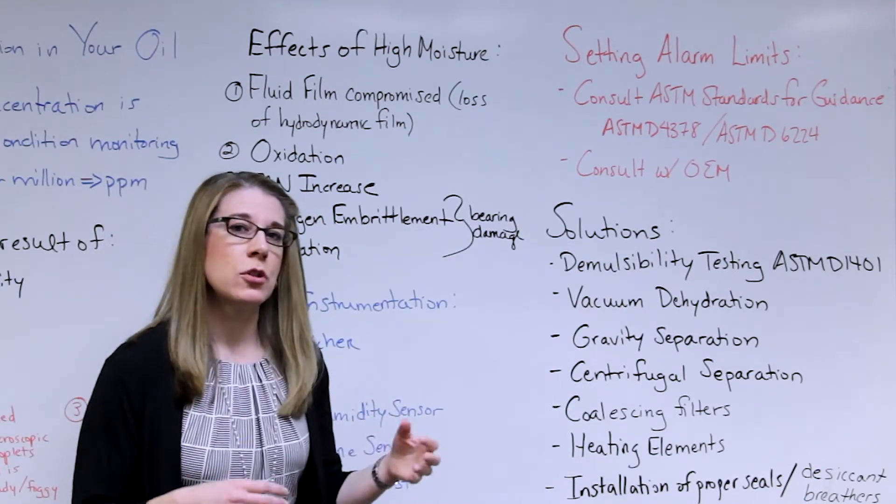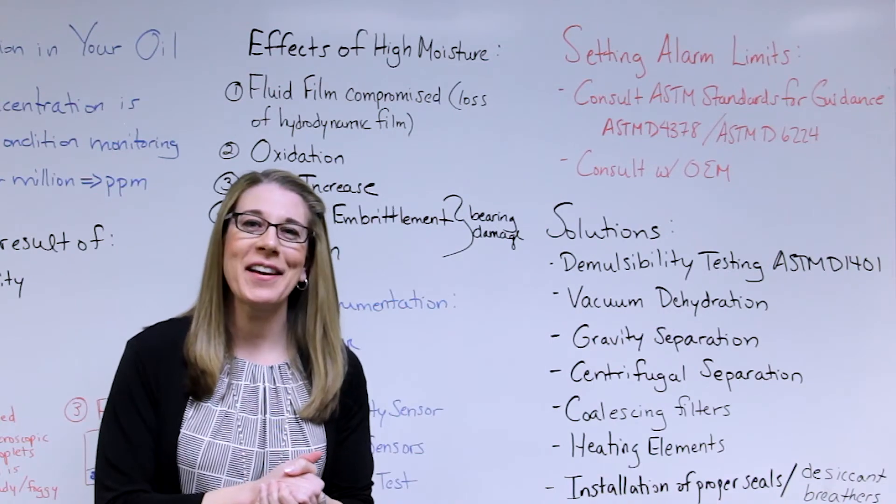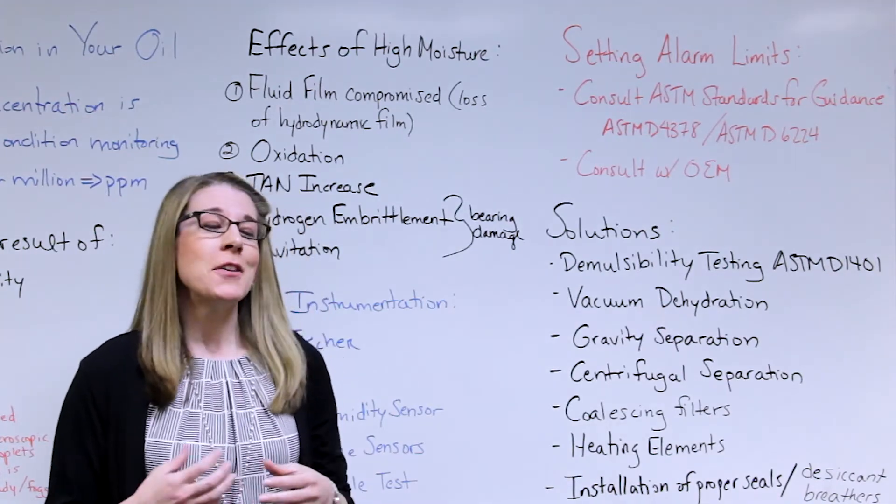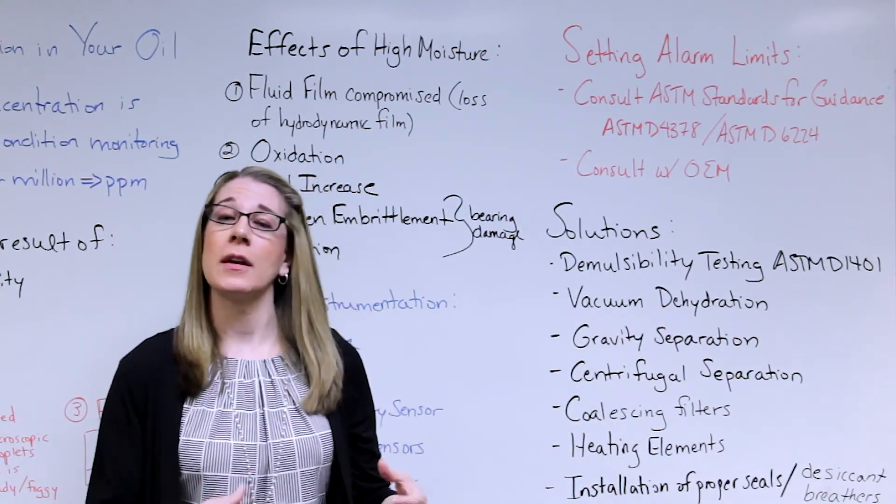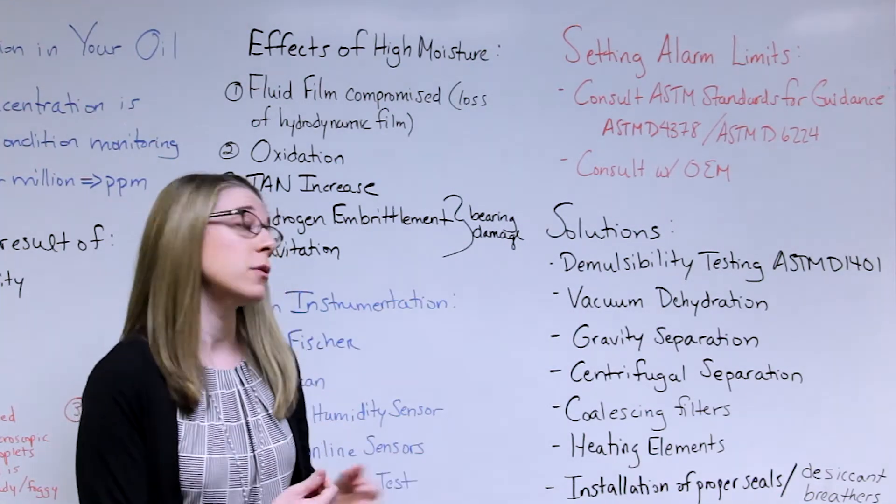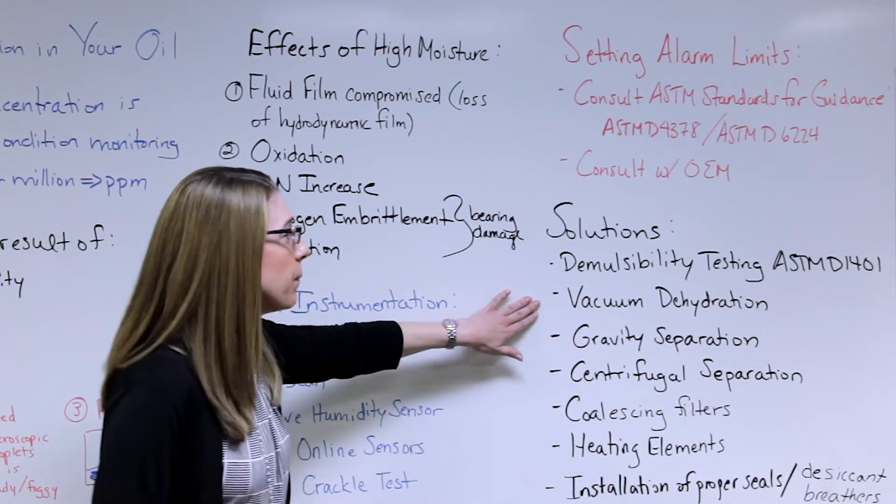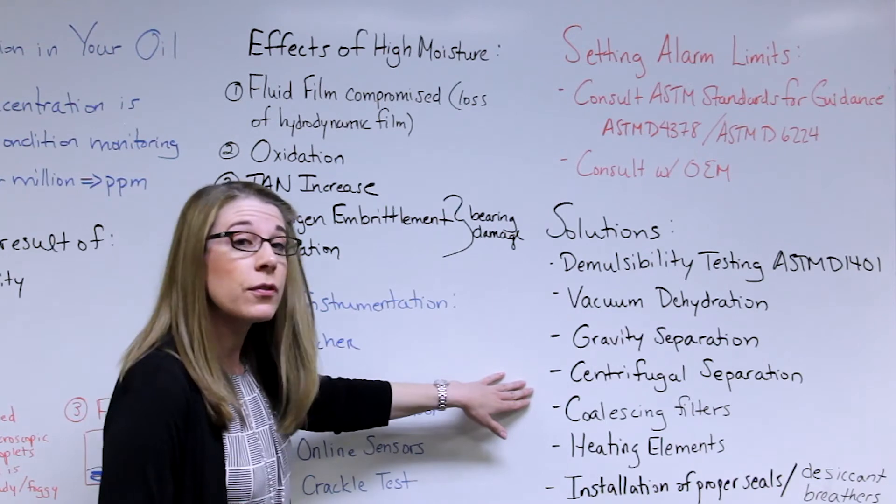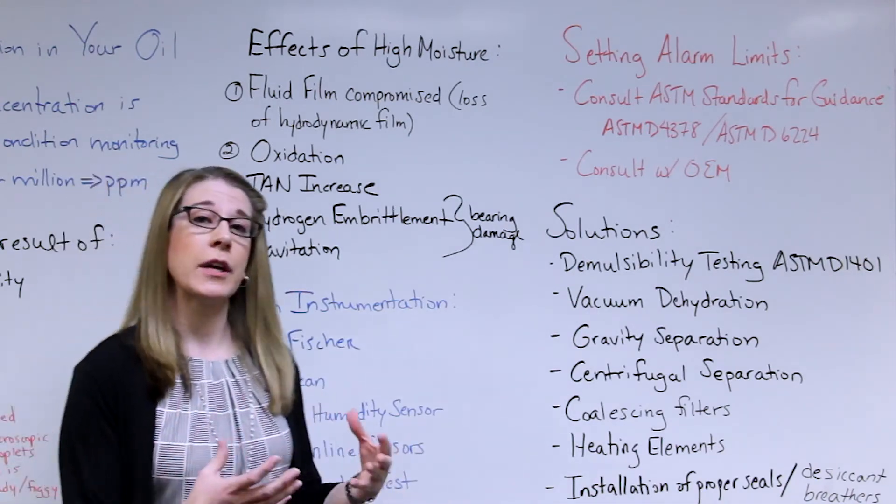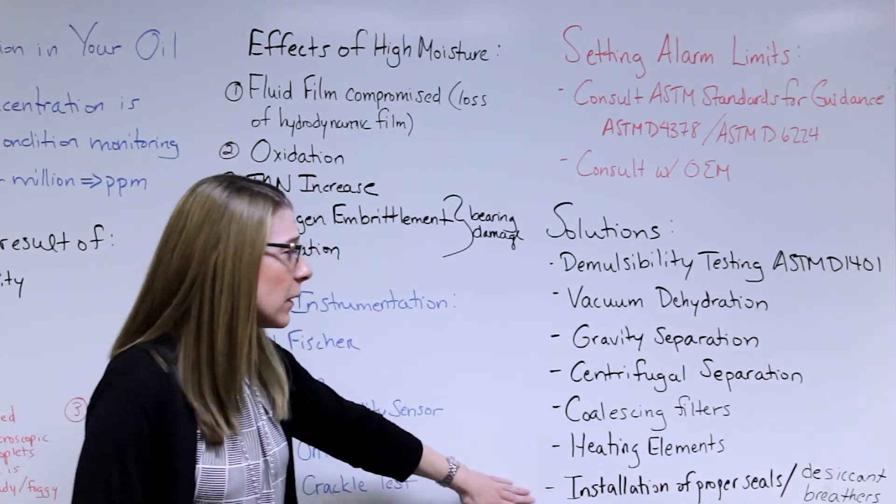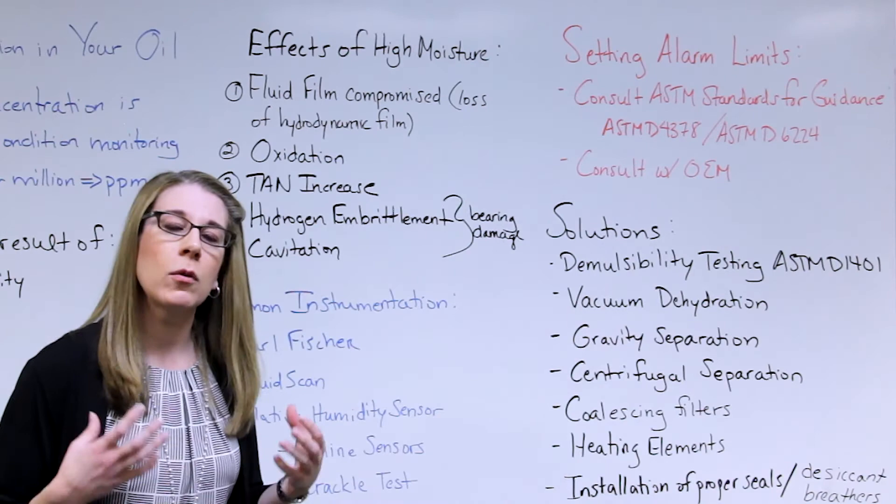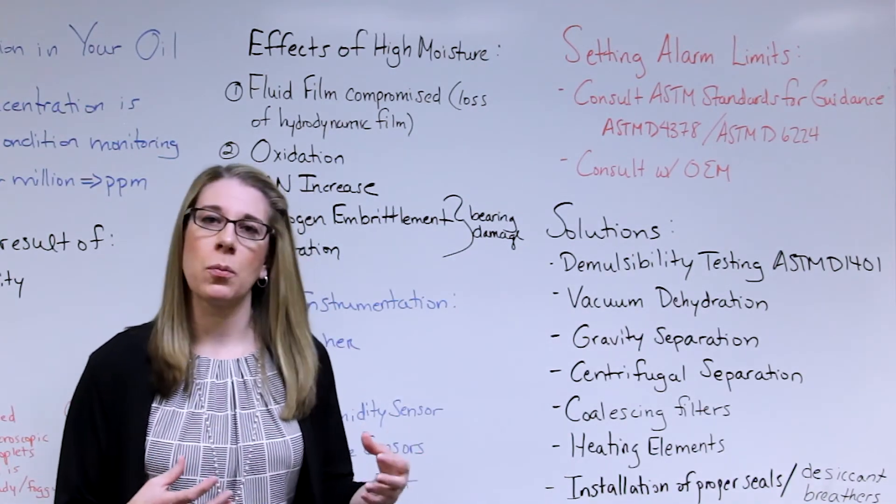Let's move on to solutions. Once you get a high reading back, now what? As the reliability engineer on site, you have a lot of different options depending on how much money you want to spend, how much time you have, and the criticality of the component. There are different options for dealing with high moisture levels: vacuum dehydration methods, gravity separation, centrifugal separation, coalescing filters, heating elements. Lastly, once you get this problem solved, you want to go back and look at your maintenance program. How are the seals? How are the desiccant breathers? Do you have desiccant breathers installed on the component? Review those maintenance practices once you get the problem solved.